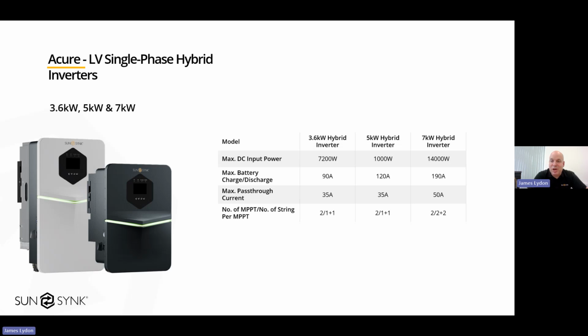You've got your max battery charge and discharge on the 5 kilowatt, which is 120 amps. When you do the calculations on that at 48 volts, it's the rated value of the inverter. And the Acure has got 2 MPPTs with 1 string into each. You can see as we get bigger to the 7 kilowatt, that has 2 MPPTs with 2 strings into each. The image there shows you the 2 different colors, the black and the white.